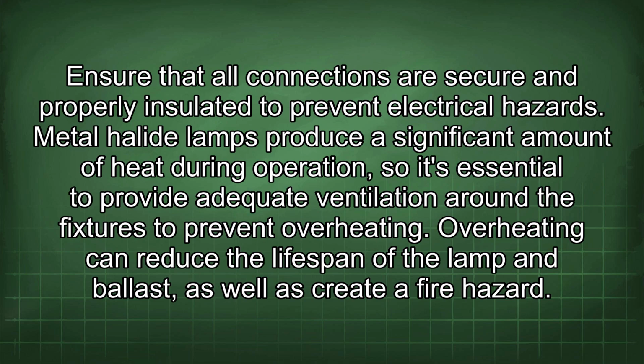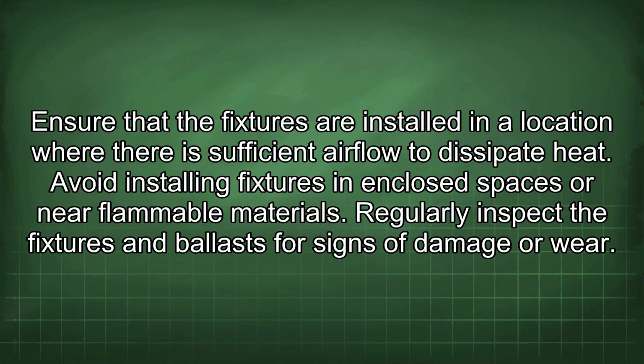Metal halide lamps produce a significant amount of heat during operation, so it's essential to provide adequate ventilation around the fixtures to prevent overheating. Overheating can reduce the lifespan of the lamp and ballast, as well as create a fire hazard. Ensure that the fixtures are installed in a location where there is sufficient airflow to dissipate heat. Avoid installing fixtures in enclosed spaces or near flammable materials.